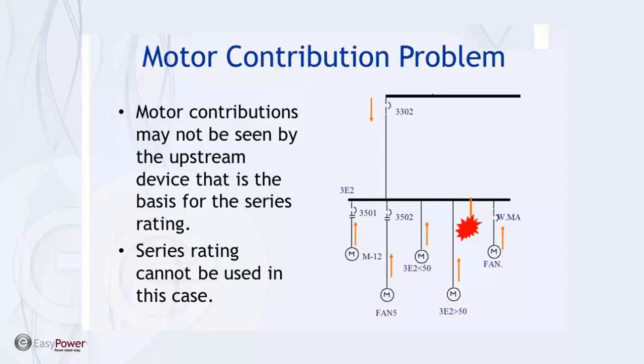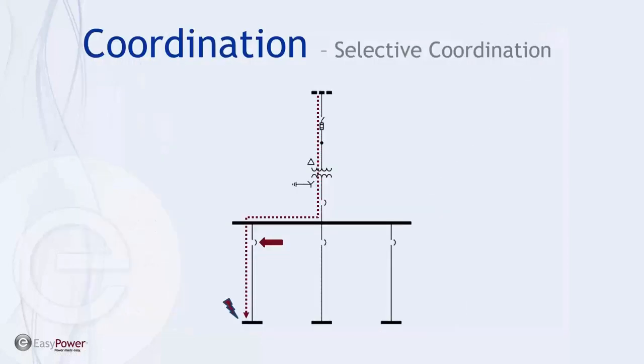It's all about equipment duty. Let's get back to coordination — a different topic, but they're tied hand in hand. If we're not properly rated, coordination is out the window anyway. Coordination basically says: for a remote fault, we want the protected device closest to the faulting element to trip first before any other device upstream can clear the fault.